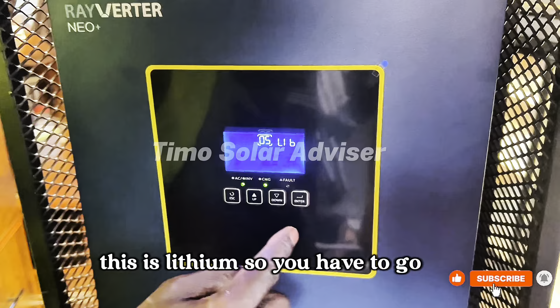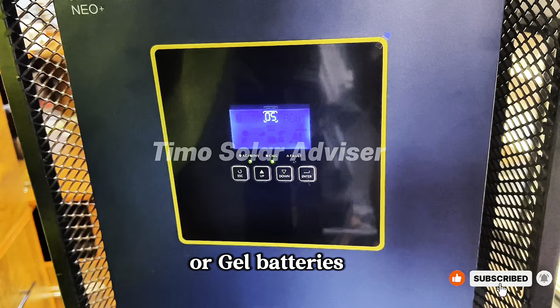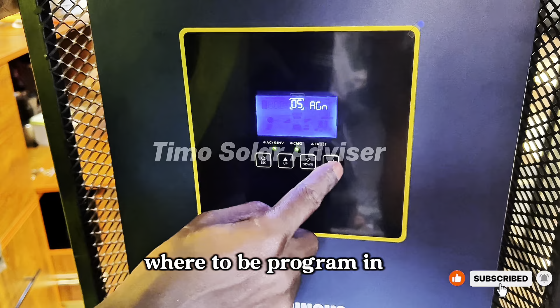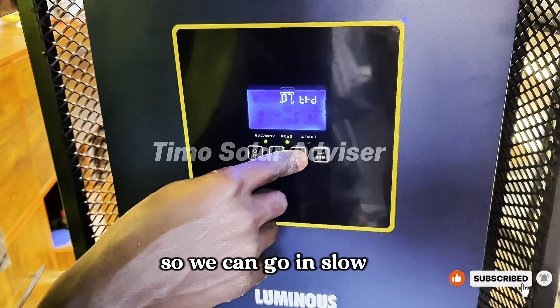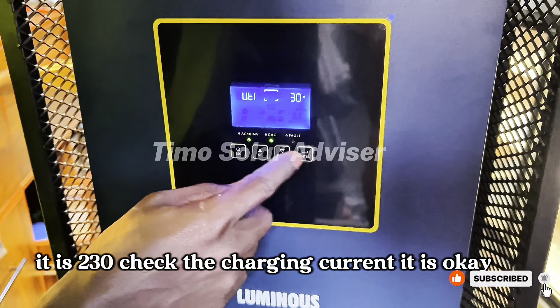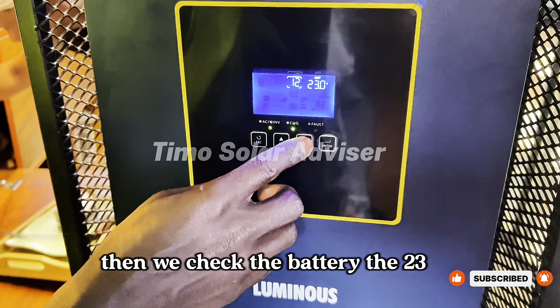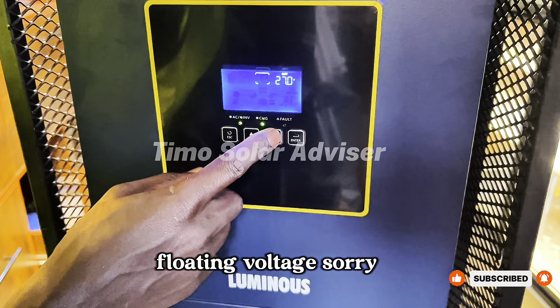This is the lithium. So you have to go until we find AGM. This is a maintenance-free battery. These are good batteries. So this is where it is programmed. Now we can enter, then we can insert the program. So we can go through. We check the output voltage, it is 230. We check the charging current, it is okay. Then we check the battery, it is 23. Then we check the floating voltage, it is 27.